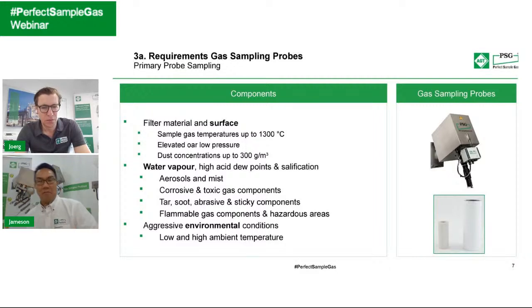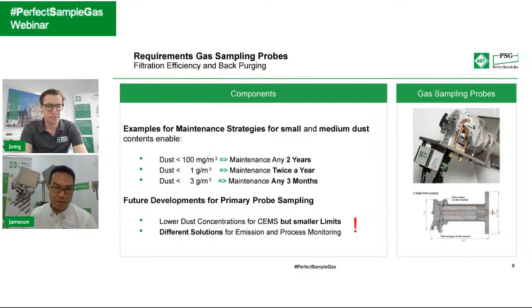And then, the whole main purpose of the sample probe is to siphon the gas in such a way, because the pump is downstream, to separate the water and the dust. All right, to separate the water and the dust so that the sticky dust will not be able to stick onto the filter element. This again, we're going to address, and all these things, what we call the quick fix, I'm going to give you the straight answers without beating around the bush.